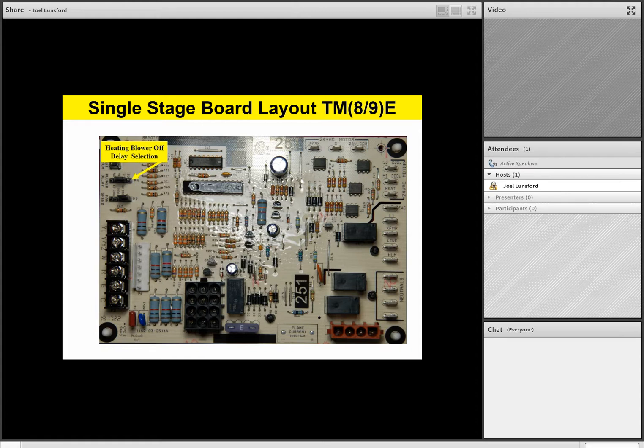Right above that is our heating blower off delay selection. We normally set that between 100 and 120 seconds from the factory. In our example, we see that our field selectable options are 60, 90, 120, and 180 seconds. And we typically set those between 100 to 120 based on the board, if 100 seconds is the jumper selection.